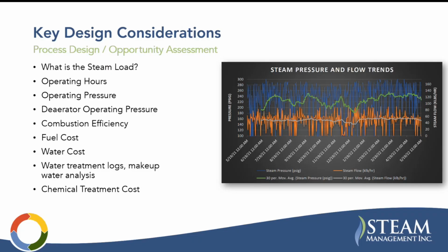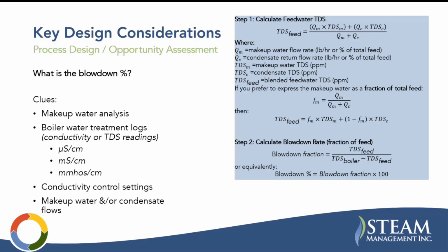And then you're going to want to get your hands on water treatment logs, makeup water analysis, things to do with the quality of the water, so you can get some clues as to how they're operating their blowdown. But overall, I would say the number one piece of information you want to know, in addition to just general steam demand, is your blowdown percentage. And the clues here are going to be your makeup water analysis. Even better than that, I would say, are the boiler water treatment logs, because you might just straight up have conductivity or TDS readings on those. Conductivity controller settings, and makeup water and or condensate flows.